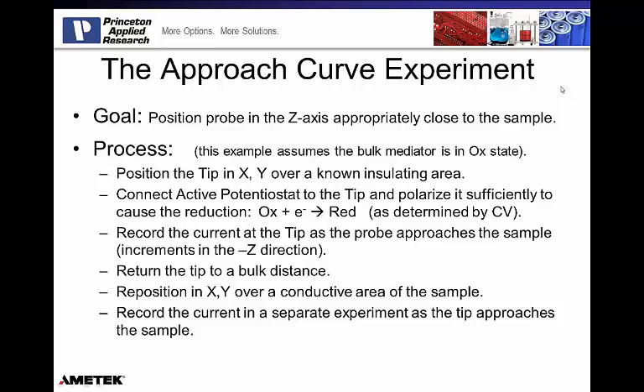Then I take this probe and return it back to the bulk distance. Then I reposition it over X and Y in a conductive area of the sample and run that same experiment again. I then overlay those two approach curves, and that tells me where to position the probe for my line scans or area scans, and it also gives me an idea of what kind of responses I can expect.